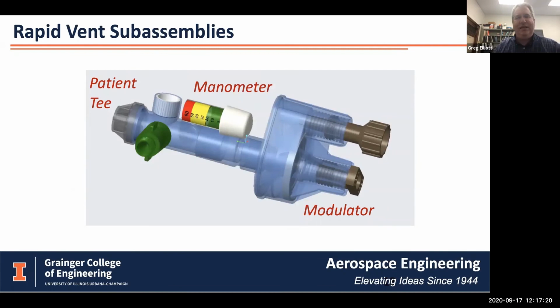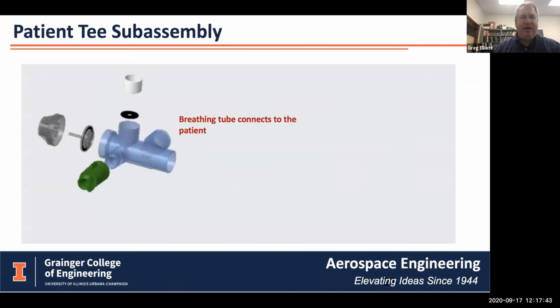We have the patient T, the location where we hook up to the oxygen supply and to the patient. The manometer is just a simple pressure device that you can look at to see what the PIP and PEEP pressures are. And then the modulator, which was something I was put in charge of on the project. For the patient T sub-assembly, there's a breathing tube that fits up to the oxygen tubes the hospital already uses, which connects to the patient.